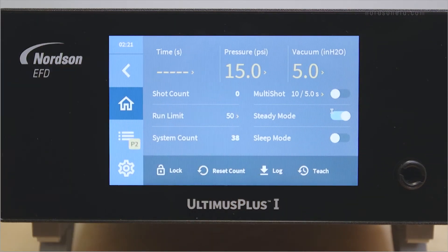By pressing the steady mode switch, you will change your Ultimus Plus from timed mode to steady mode. When the switch is off, you will be in timed mode and your Ultimus Plus will dispense for the indicated amount of time. When the switch is on, you will be in steady mode and the Ultimus Plus will dispense while it receives the signal to do so, whether that's from a foot pedal, a switch, or from an external control.